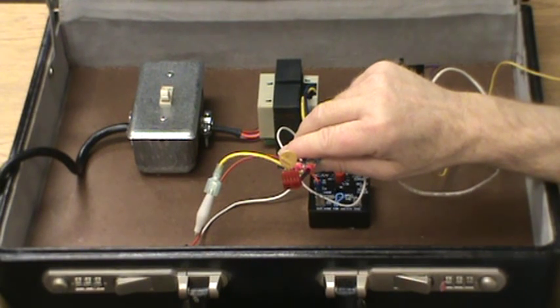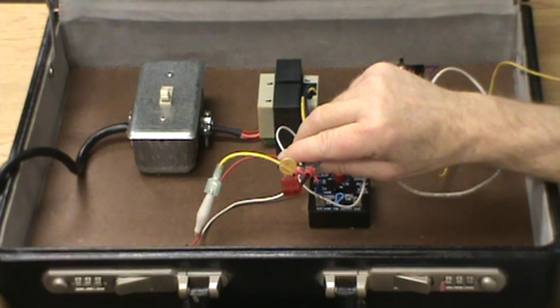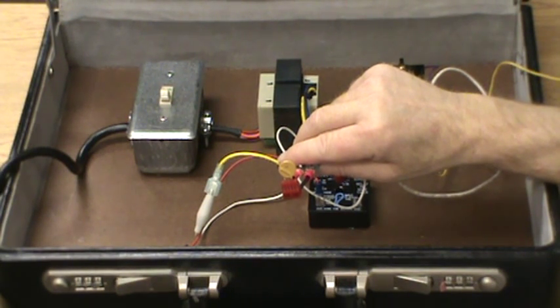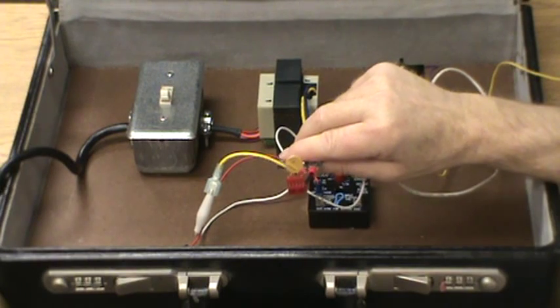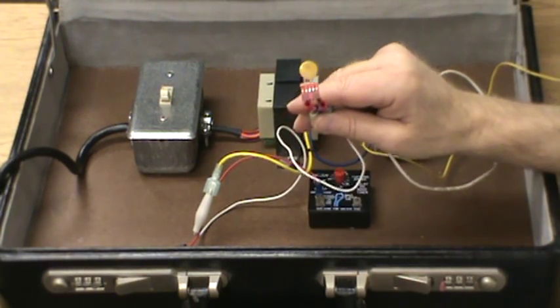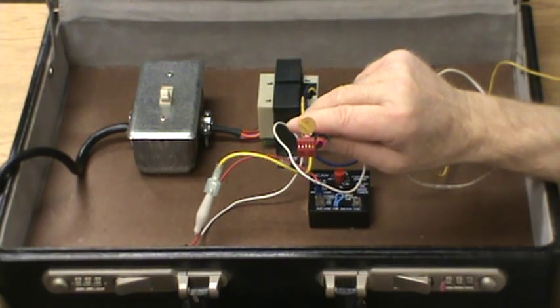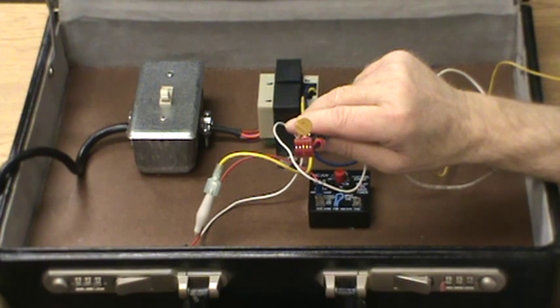Then if you can't find the short, you're going to be second-guessing yourself, thinking it could be the thermostat or the circuit board. Unless you can locate that short, the best thing to do is to install one of these resettable fuses. It can be wired to stay in a lockout mode like a traditional fuse and stay open until you go out there to do the repair.